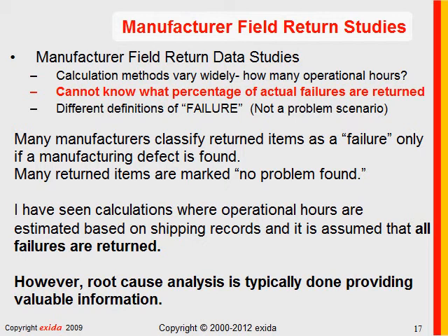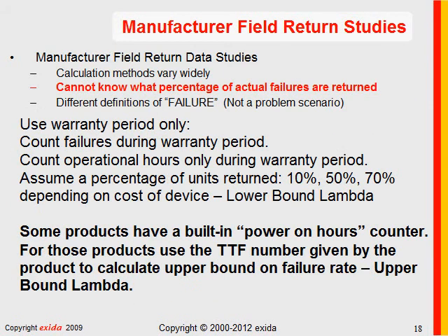However, the beauty of this is when a real failure is found, the root cause analysis is done well. Most manufacturers trace the cause of a problem back to the specific component and the failure mode of the component. So this data is not necessarily useful for calculating absolute failure rates, but it is useful for determining failure modes of components. It's very valuable for that.